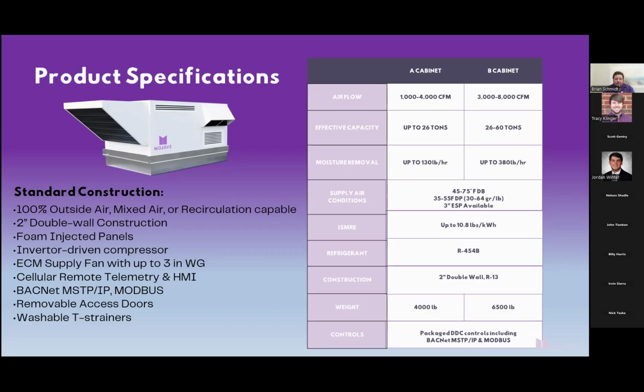We do have the capability for BACnet and Modbus. Every one of our access panels is fully removable. We have 4 hinges on each access panel, which makes it very nice for maintenance. And we do have washable T-strainers. So I mentioned before, the A cabinet is from 1,000 to 4,000 CFM. B cabinet is 3,000 to 8,000. As you can see, at the highest, our moisture removal capability is 380 pounds per hour. It's a lot of water.